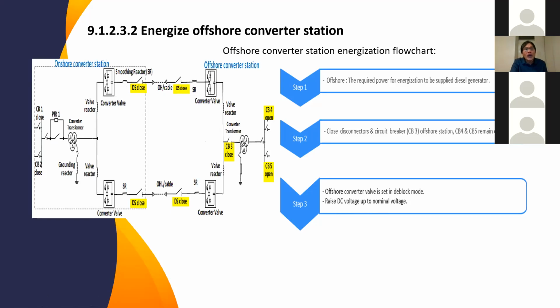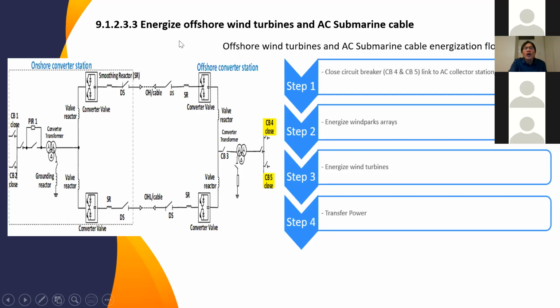We move to the next one, the last one, to energize the offshore turbine. So we did energization onshore, we did energization offshore. All circuit breakers here, circuit breakers 1, 2 still remain closed. Disconnector remains closed. CB here remains closed. Now we close CB4 and CB5. By this, we energize the wind farm, we energize the wind turbine and transfer power. The purpose of the power transfer here is only for auxiliary power, in order to help the turbines energize themselves. So we will not transfer big power to the turbine here. This is only for auxiliary supply.